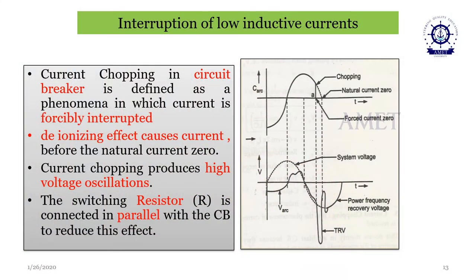We know very well, with a very simple resistor switching, we can incorporate a simple resistor connected in parallel with the circuit breaker contacts, along with that we connect one resistance in parallel, not in series. In this way, the overvoltage is absorbed by the additional external resistance, and this is a very effective and simple method for suppressing and controlling the current chopping method of generation of overvoltage.